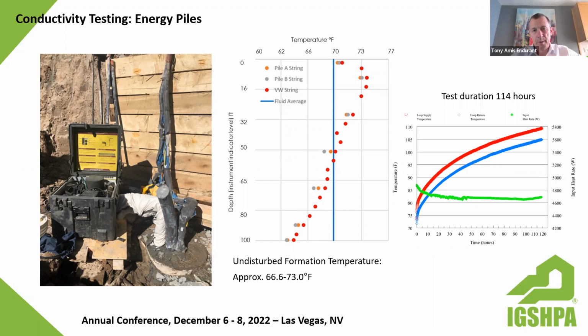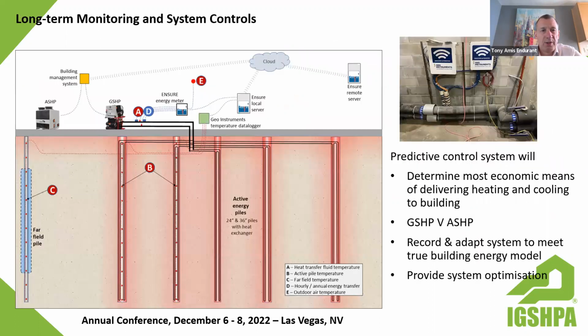The idea would be that we review that and modify the system accordingly. Through the control strategy, we're sending signals to the heat pumps on the roof saying yes, we've got availability to deliver heating or cooling today. The heat pumps themselves will be measuring air temperature, we'll be sending ground loop temperatures, and by a quick calculation we can work out what the best COP is for operating either ground source or air source heat pump mode, ultimately delivering a low cost energy heating and cooling solution to the building owner—and also low CO2 emissions. So it's very important to manage and maintain through the life of the building.